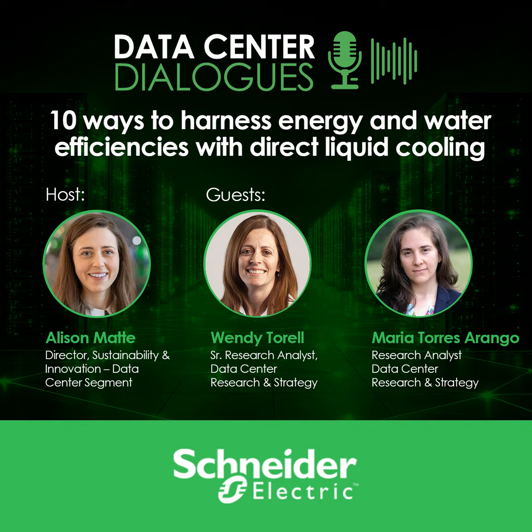Alison, that's an important distinction. Liquid cooling isn't new, but the need for it has definitely changed. And what's driving this need is server power density. GPU-based servers are drawing far more power and generating far more heat than traditional CPU-based systems. Once you start getting into densities above what air cooling can handle efficiently, you have to rethink how the heat is removed. Direct liquid cooling does that by circulating a coolant through cold plates that sit directly on the hottest components, the GPUs, and the heat is then carried away by the coolant rather than trying to move it with massive volumes of air. That shift creates real opportunities to improve energy efficiency, and in many cases water efficiency too, especially when you step back and look at the entire cooling facility from the chip all the way to the outdoor heat rejection.